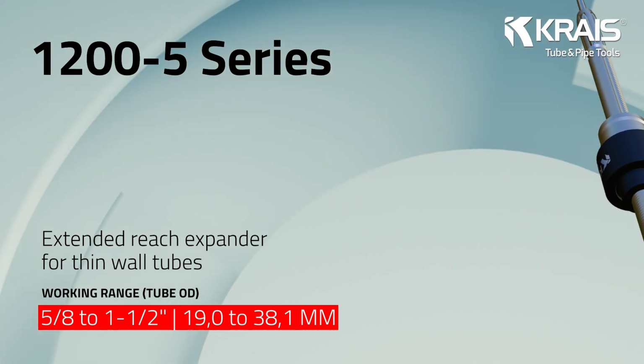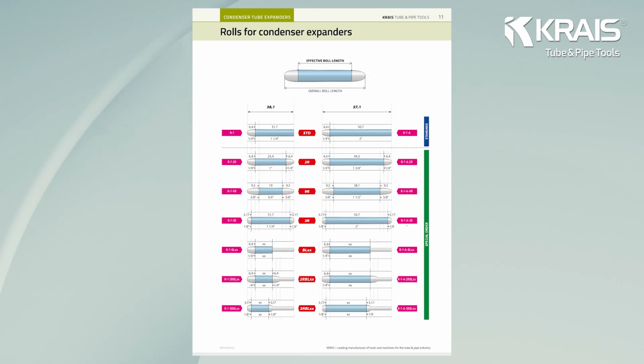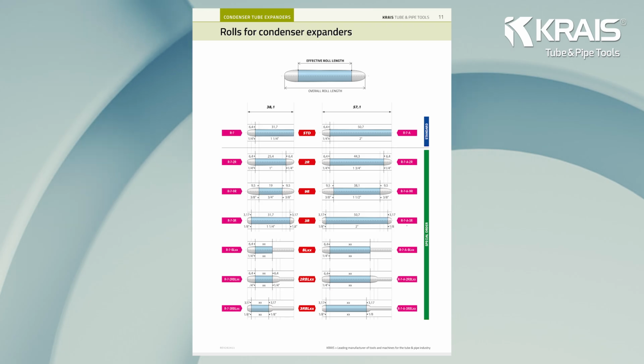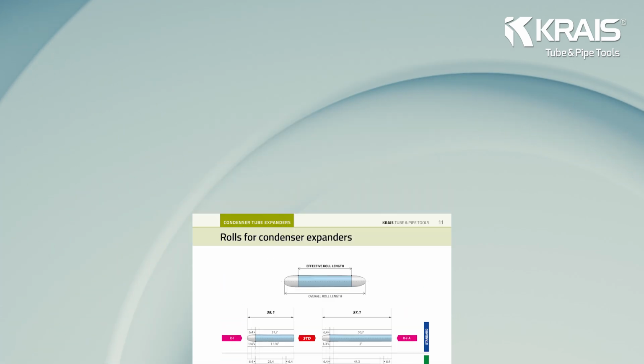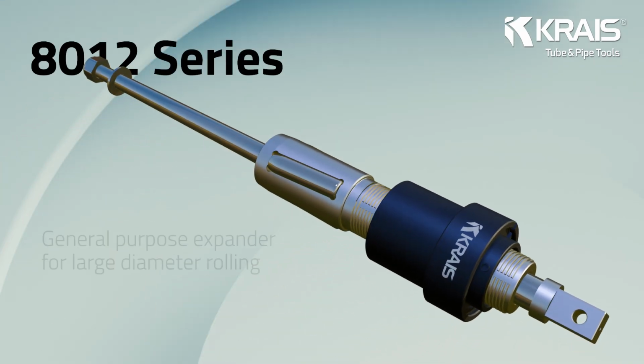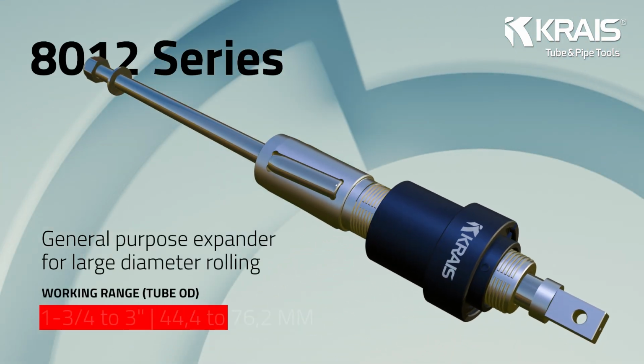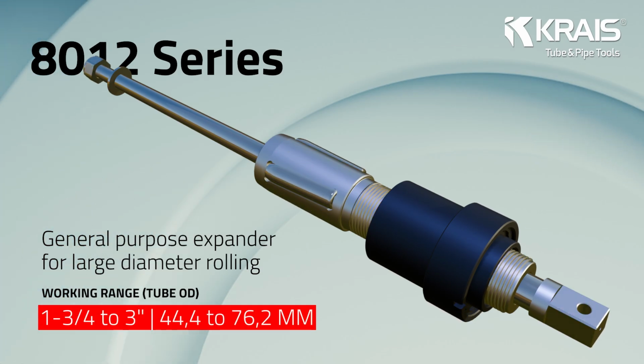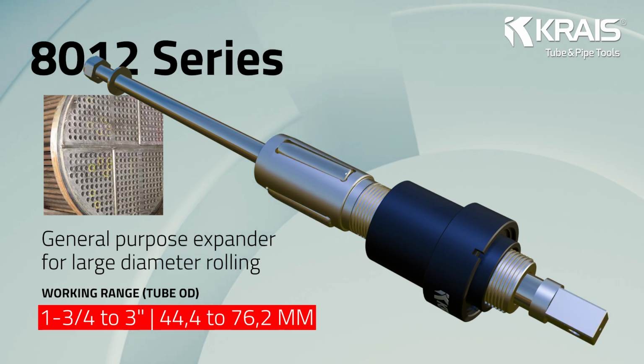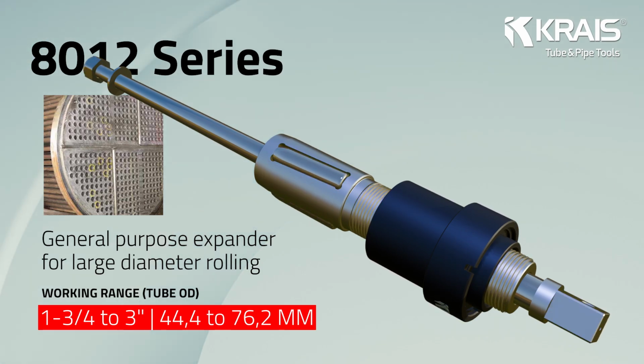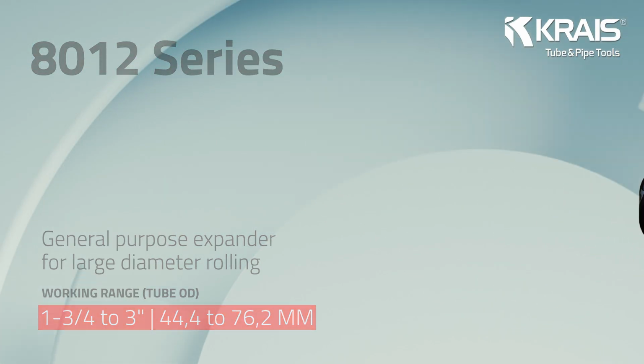gentler, more controlled expansion. For all of the 800 and 1200 series, we offer various roll shapes, like double radius for step expanding or expanding after welding. KRAIS 8012 series expanders are intended for larger tube diameters in heat exchanger work, where the 800 and 1200 ranges are no longer sufficient, but you still require controlled expansion for exchanger joints.